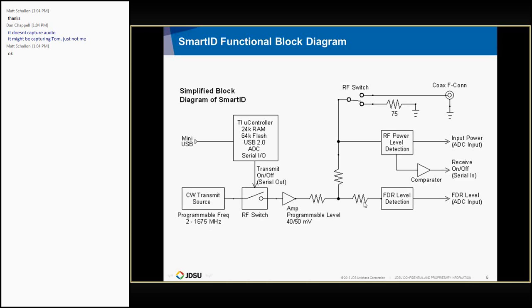And over to the right, there's a power detector that receives the input from the F connector, runs it through a comparator. That's the receive side of the signaling, and that's how these probes communicate with each other when they're not actually running a test. The RF power level detector is used not just for receiving the signal and indicating an on-off condition, but it's also used for an accurate power measurement across a broad band. It has a pretty good range of capability there.